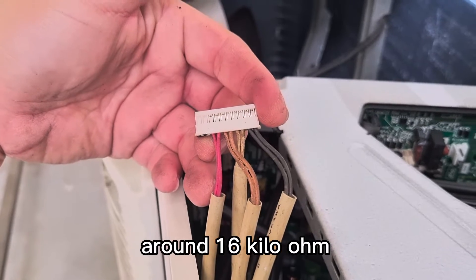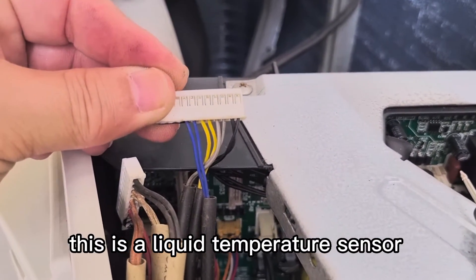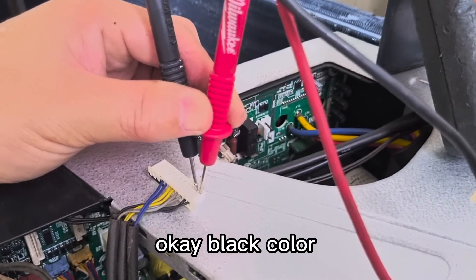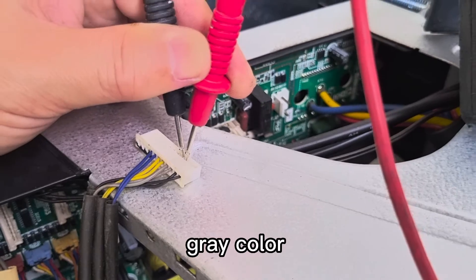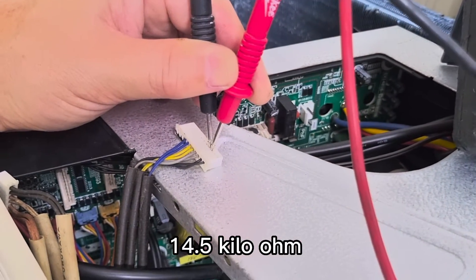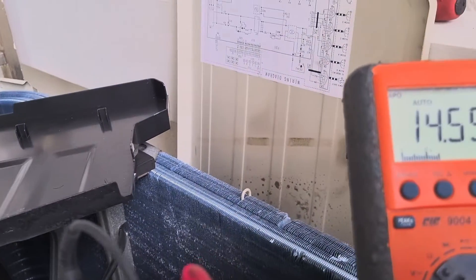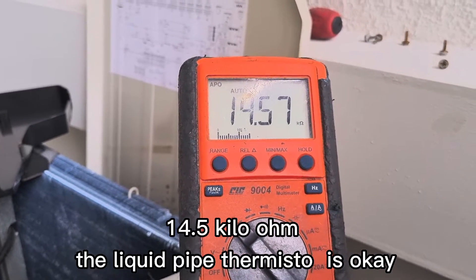Normally around 16 kilo ohm. Black color: 14.2 kilo ohm. Gray color: 14.5 kilo ohm. Yellow: same, 14.5 kilo ohm. Last one is blue: 14.5 kilo ohm. The liquid pipe thermistor is okay.